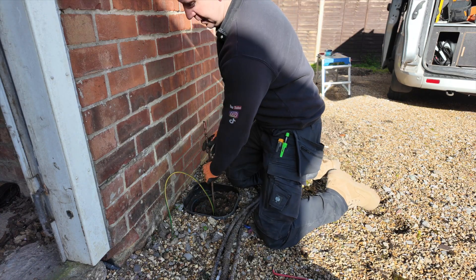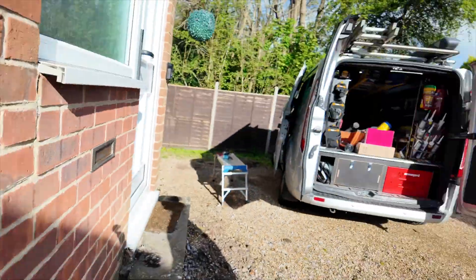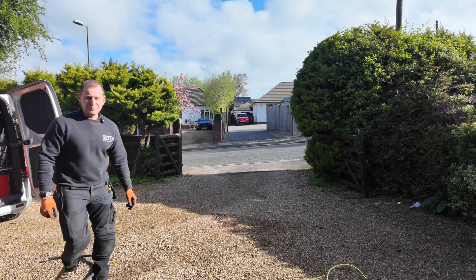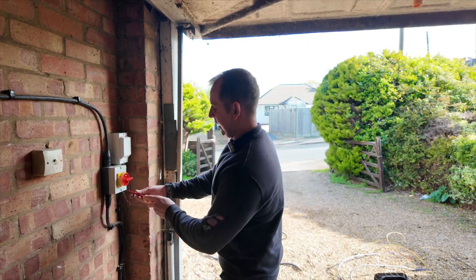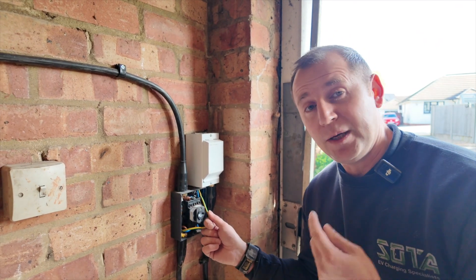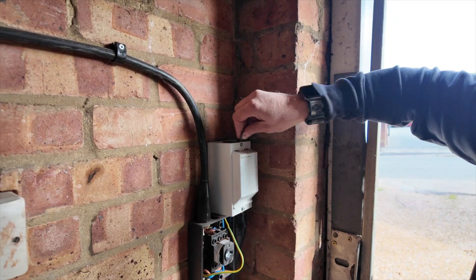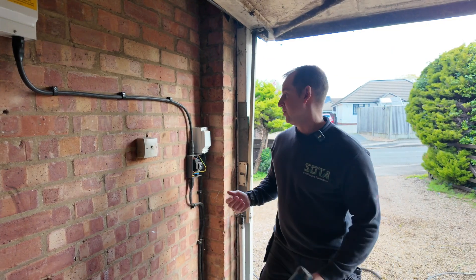That just came off — completely loose. Let's have a look in here then. To be fair, the armoured cables are earthed at this end, but they weren't glanded properly at the other end. I've just spotted something — this is concerning. That's proper rough. How can you charge someone for that?